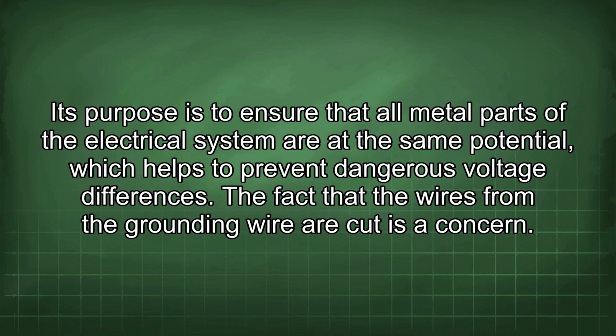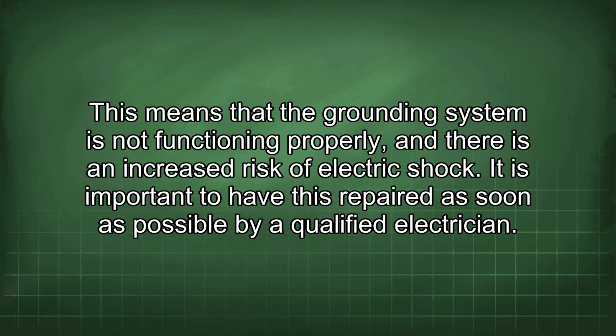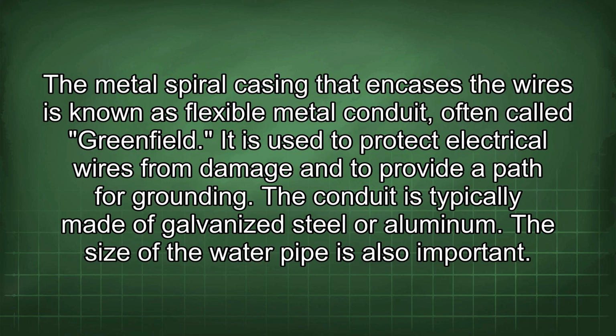The fact that the wires from the grounding wire are cut is a concern. This means that the grounding system is not functioning properly, and there is an increased risk of electric shock. It is important to have this repaired as soon as possible by a qualified electrician. The metal spiral casing that encases the wires is known as flexible metal conduit, often called greenfield. It is used to protect electrical wires from damage and to provide a path for grounding. The conduit is typically made of galvanized steel or aluminum.